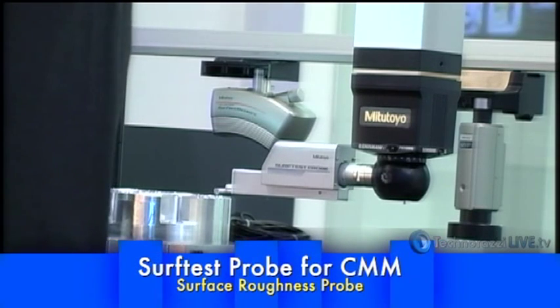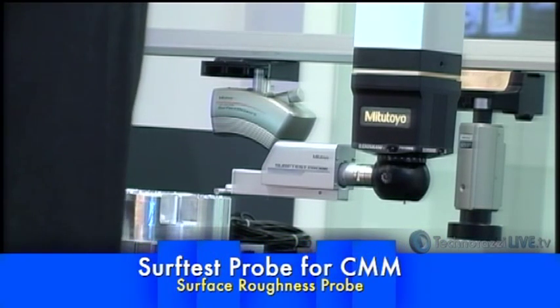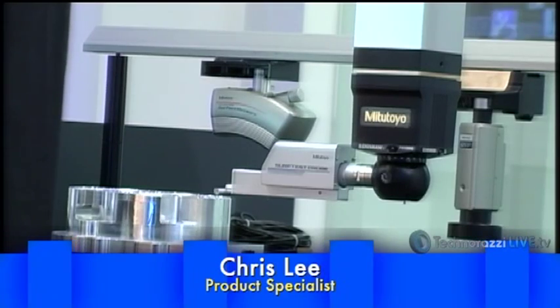Essentially, we've taken our most successful portable surface unit, the SJ210, and we've integrated it with our Crysta-Apex CNC CMM. So what we've done is, in conjunction with a PH10M probe system and rack from Renishaw, we've mounted it into it. So when deployed, the probe will go over the measurement area, it'll lower itself, and a diamond stylus makes a trace across the part and begins to take a reading. Okay. All this is programmable via our own Mitutoyo MCOSMOS and FORMTRACEPAK software.